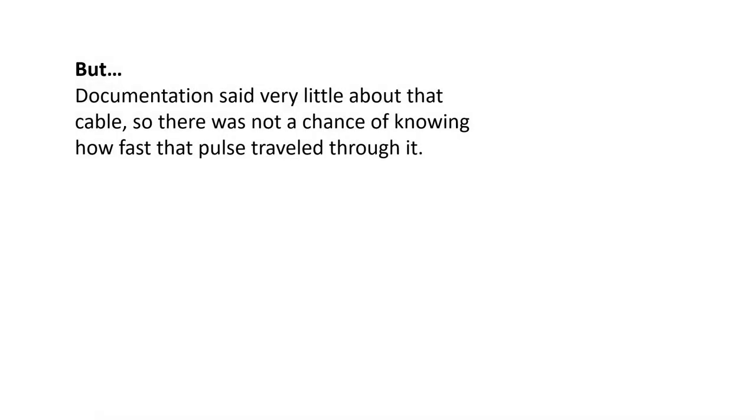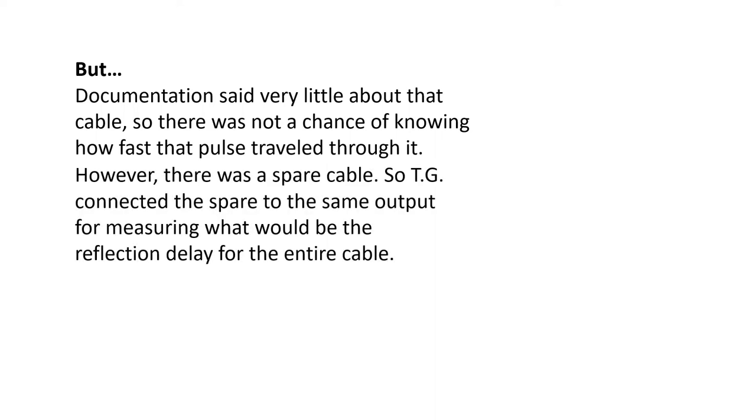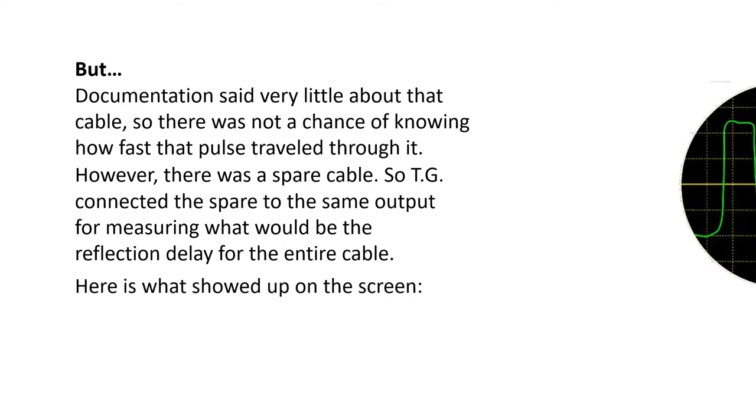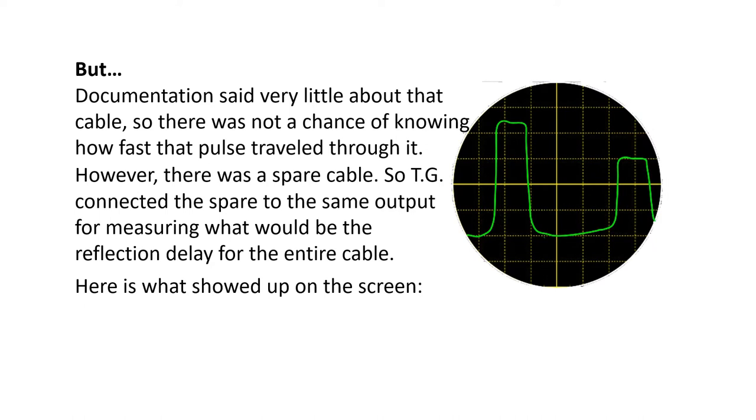But, well, there's always a but. Documentation said very little about the cable, so there was no chance of knowing how fast the pulse would travel through it. However, there was a spare cable, so TG connected the spare to the same output for measuring what would be the reflection delay for the entire cable. Here's what showed up on the screen. It could be read that the entire delay would be 4.4 microseconds plus or minus 0.05.